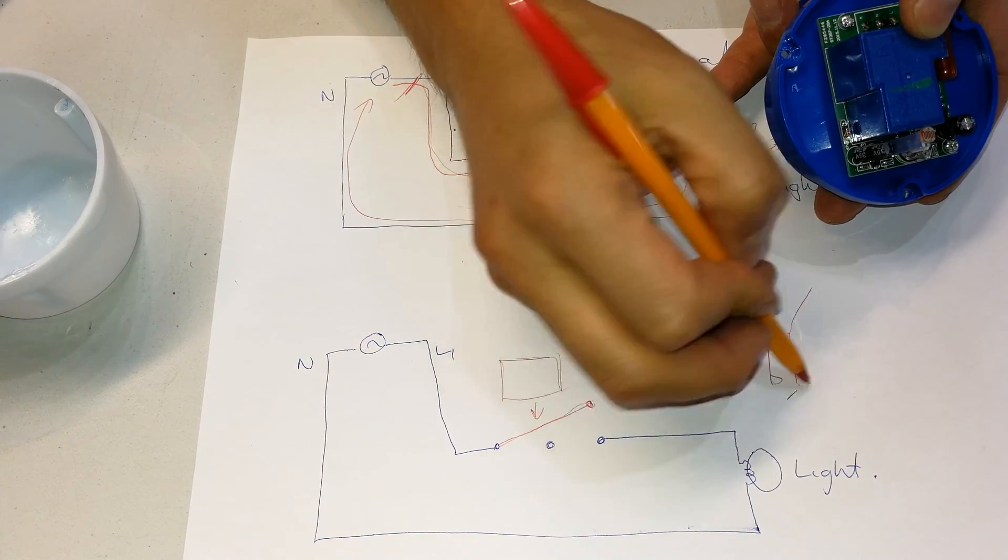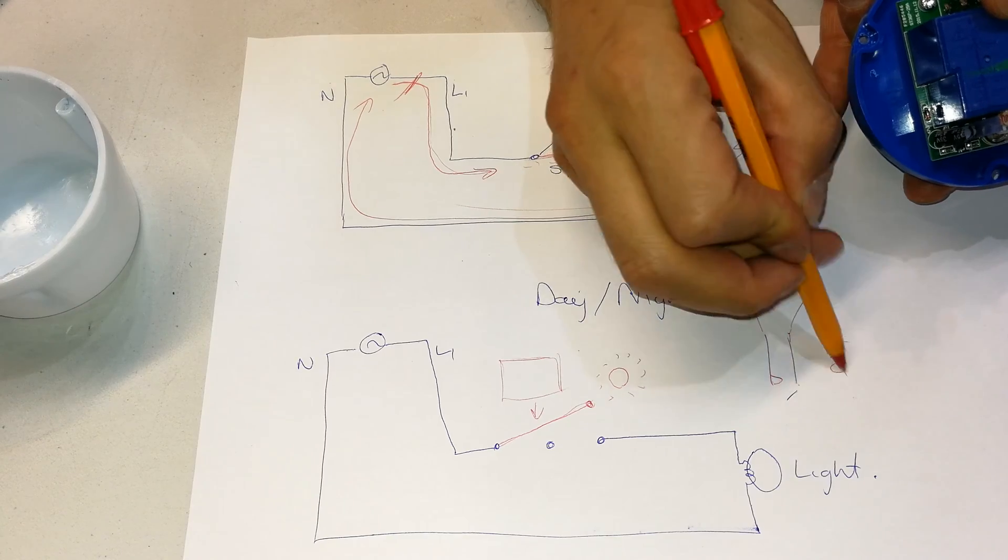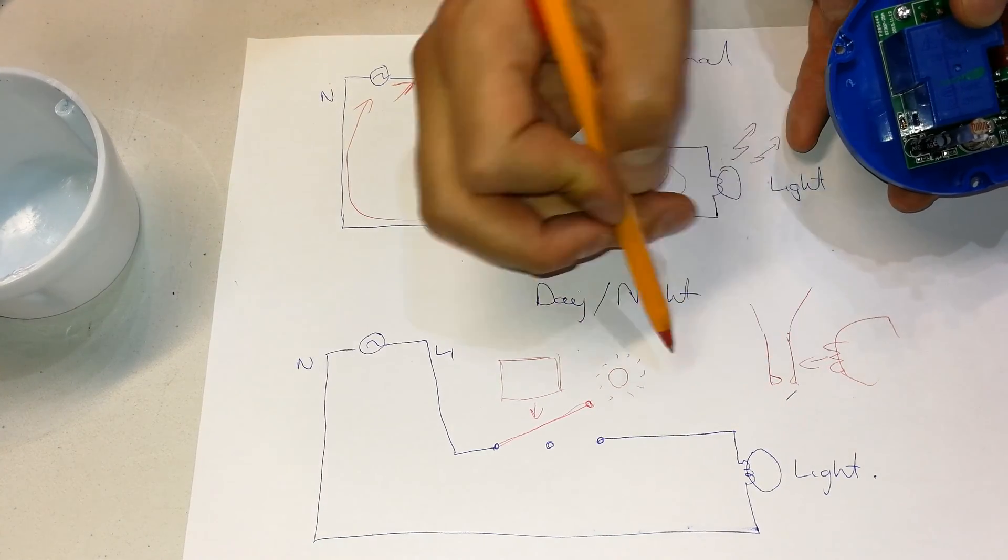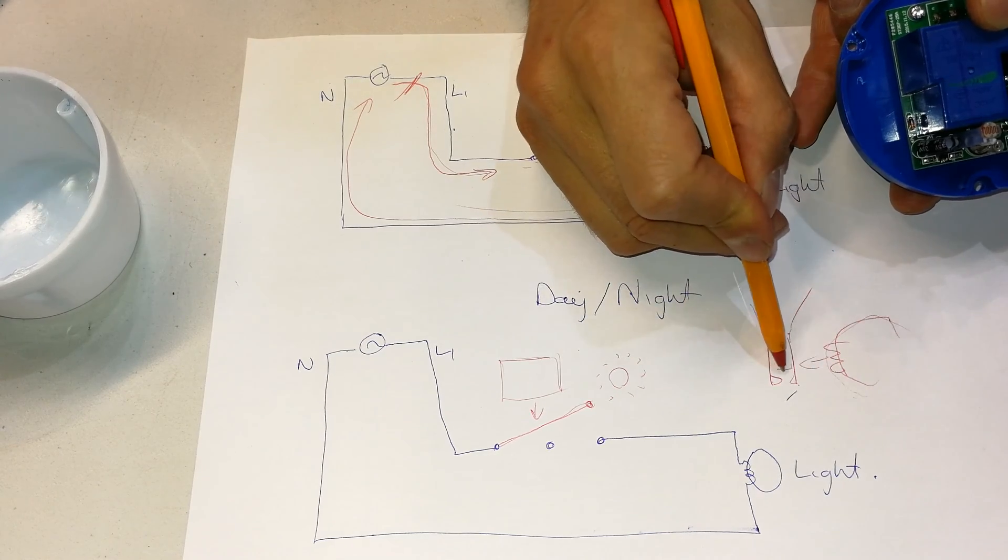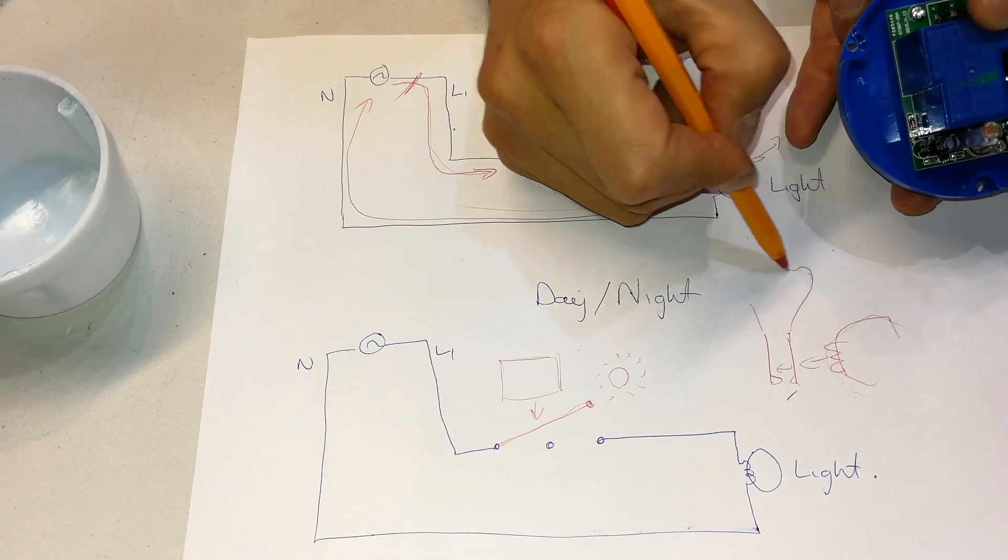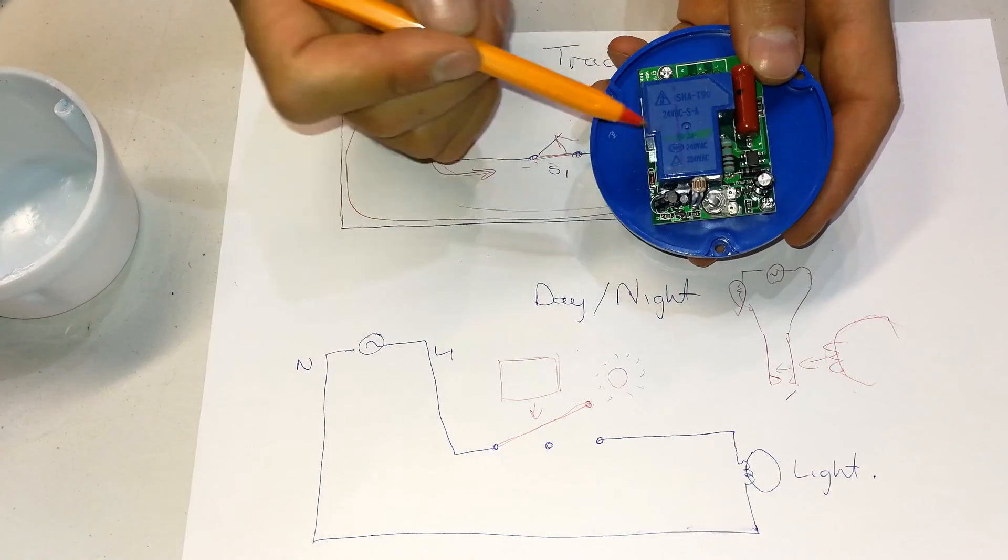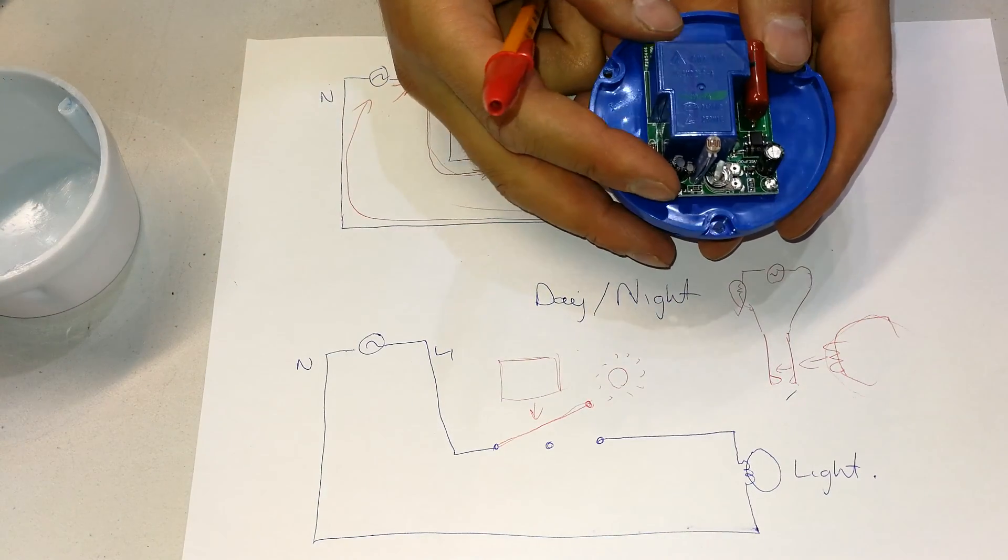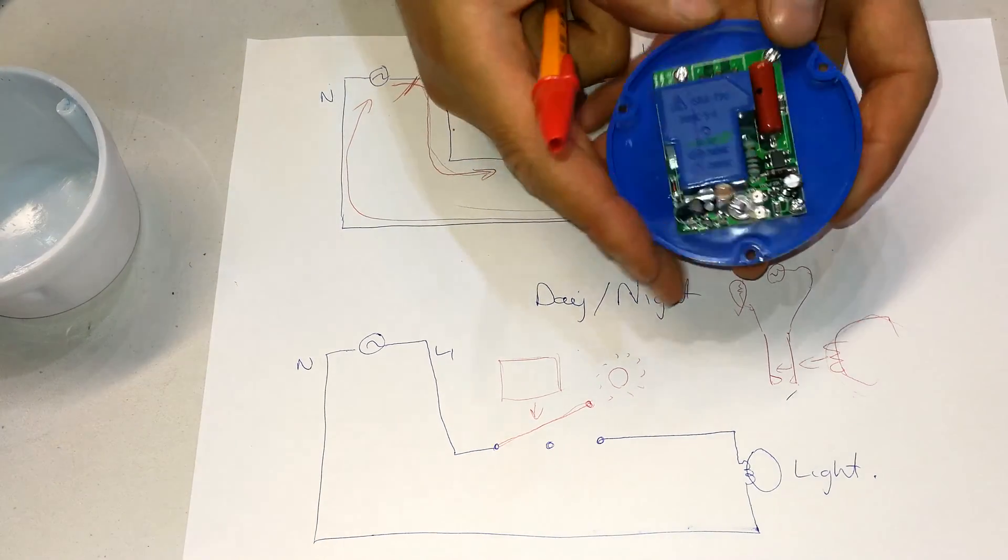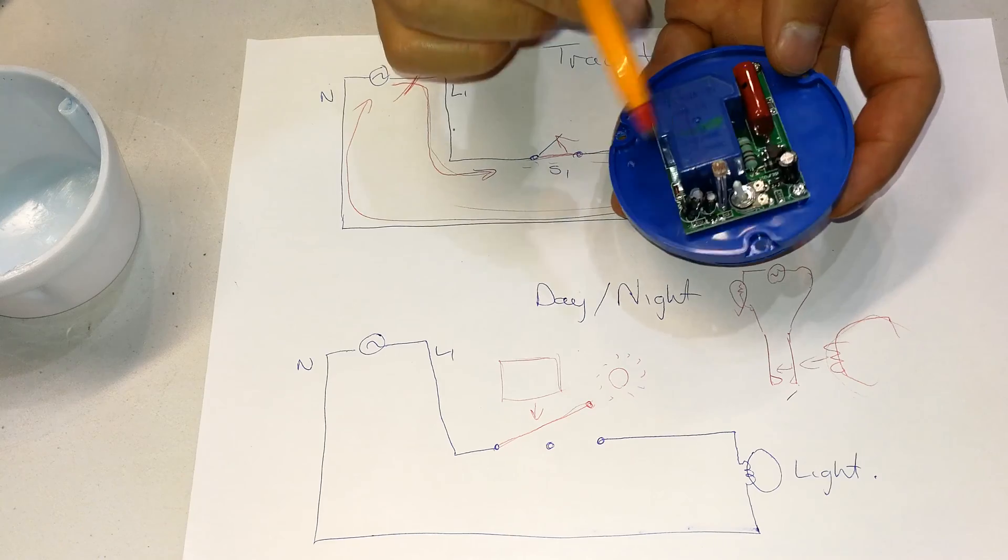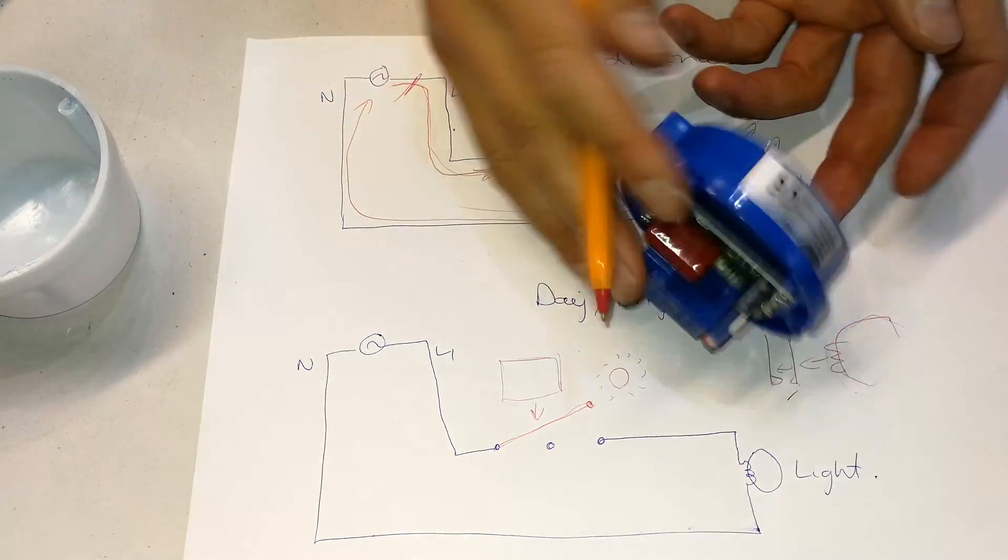That closes a circuit but using another circuit's energy to actuate it. So it means using energy from another circuit we can close the contact and allow energy to flow into another circuit. So that's what a relay is. And usually it's got an amperage—well, it's always got an amperage—and this day-night switch is 25 amps. Now what is actuating or closing this relay?